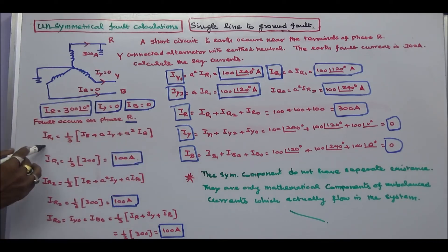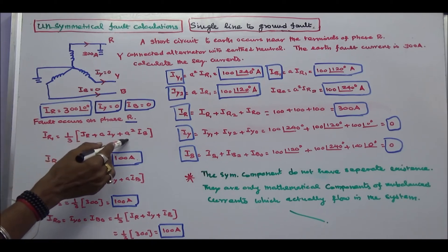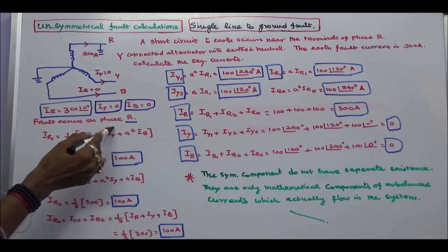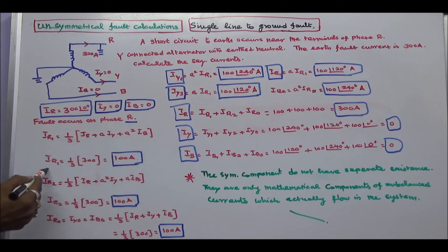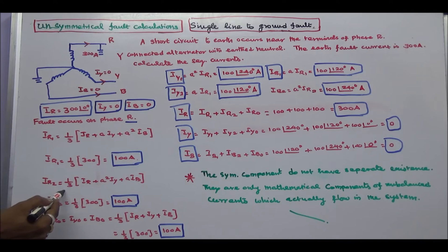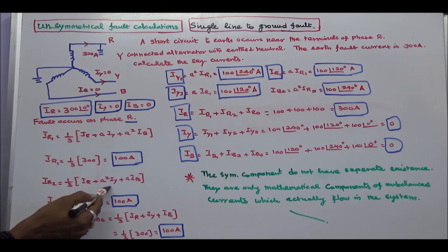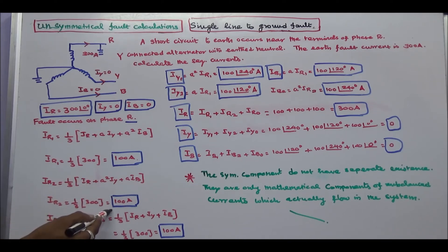Ir1 is equal to 1/3 times (Ir plus A·Iy plus A²·Ib). Since Iy is 0 and Ib is equal to 0, therefore Ir1 is equal to 100 Amps. Ir2 is equal to 1/3 times (Ir plus A²·Iy plus A·Ib). These two terms are 0, so Ir2 is equal to 100 Amps.